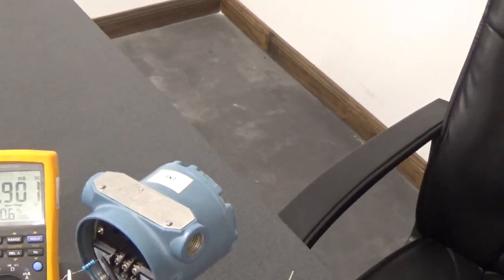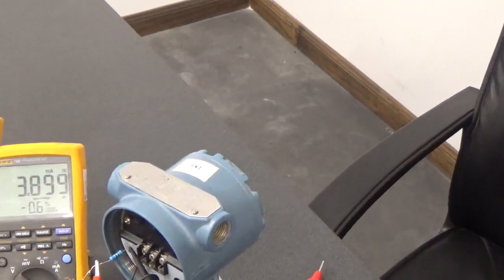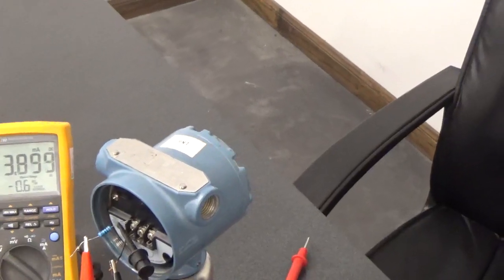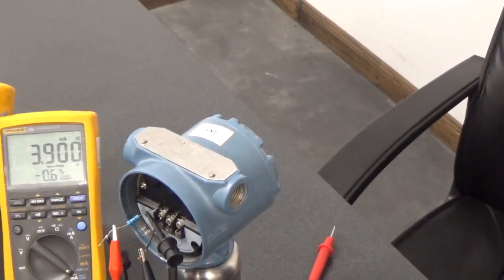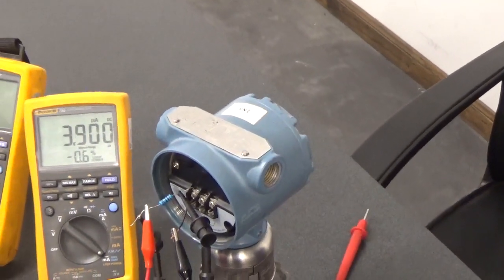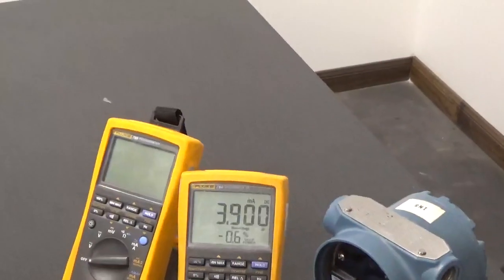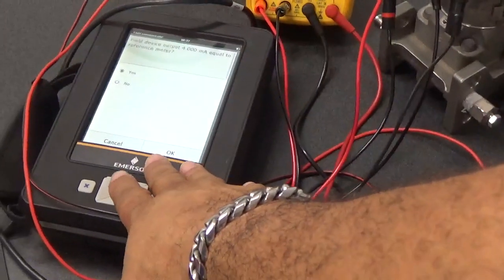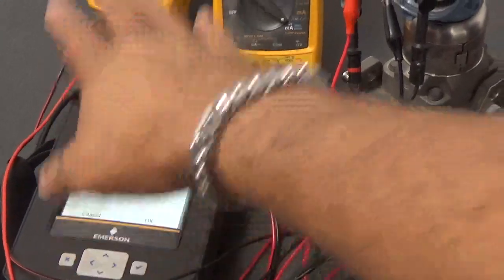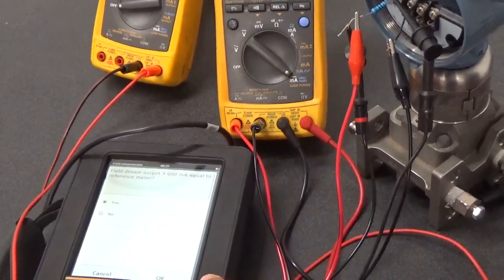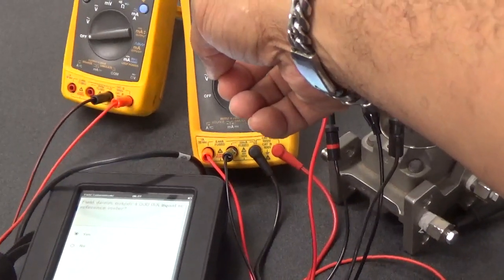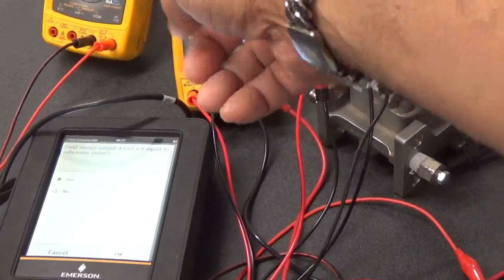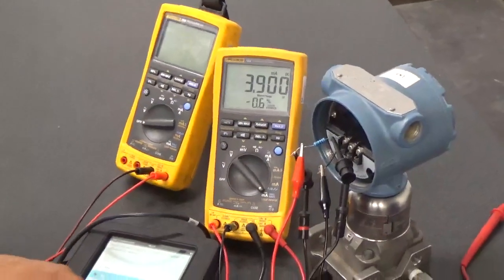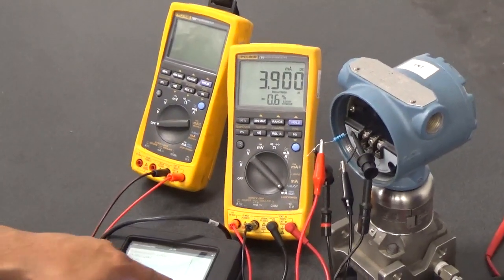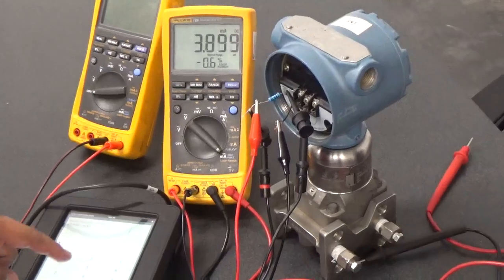Now you see how that meter? Now see, the device output right now is set at 4 milliamps, but is it reading 4 milliamps? Huh? That's why you're saying as long as there's a milliamp signal, you knew the meter was on. Yes, but look at the deal. Remember, this right here is reading a digital signal, not a milliamp signal. This meter is telling this communicator that it's putting out 4 milliamps, but we know that's not true. We know that's not true because we see it, because this is our reference meter. Now go ahead and fix it. Fix it, Raul. So you'd put the 4.1 and make it drop to 3.9? Yeah. You'd put 3.9 and it would make that go to 4.1? Yes, watch it. I just wanted you to see a bad milliamp signal.